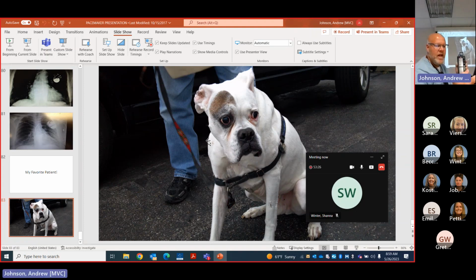The other key aspect here, and I just want to make sure I say that it is right here. So the battery in the back compartment here, good for 7 days. And you have 30 seconds. The pacemaker's still going to continue to work while the battery drawer is out. So you have 30 seconds to change the batteries if you need to. After the battery indicator light comes on, you do have 24 hours left on that.